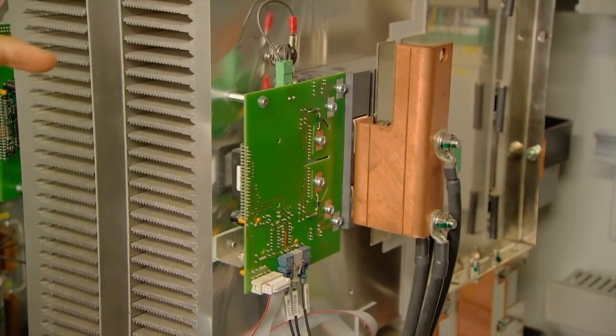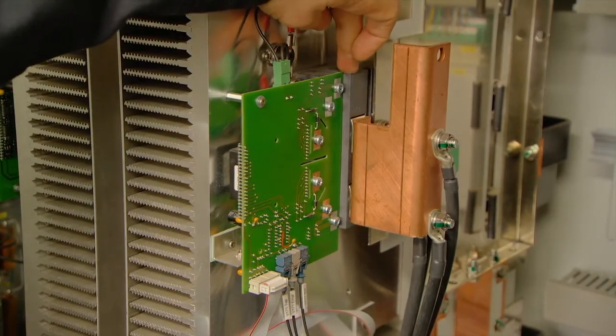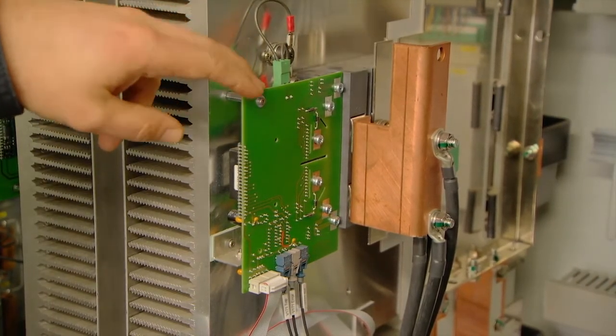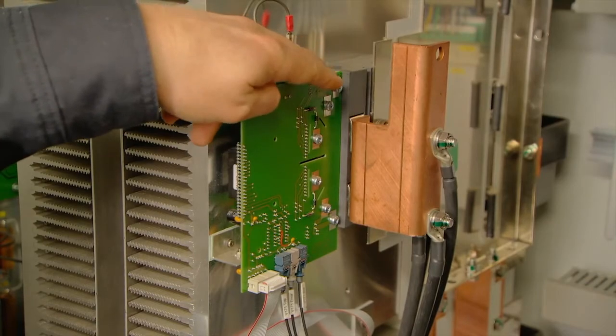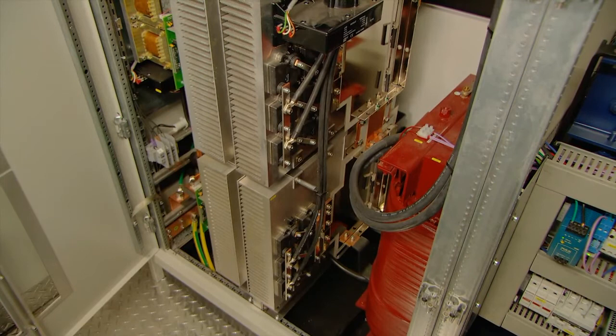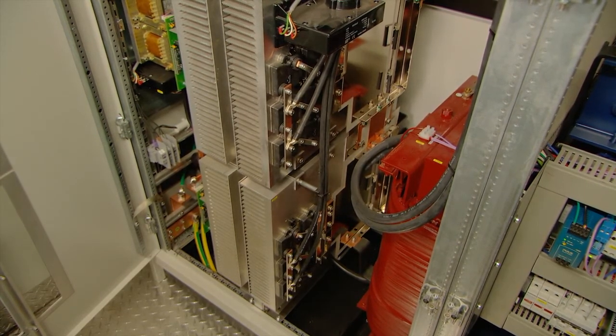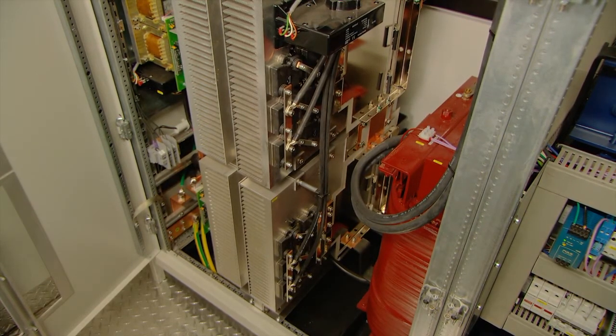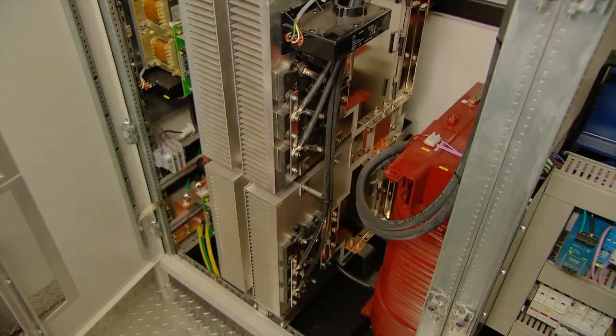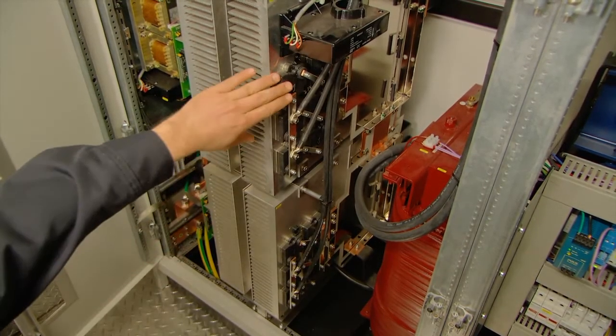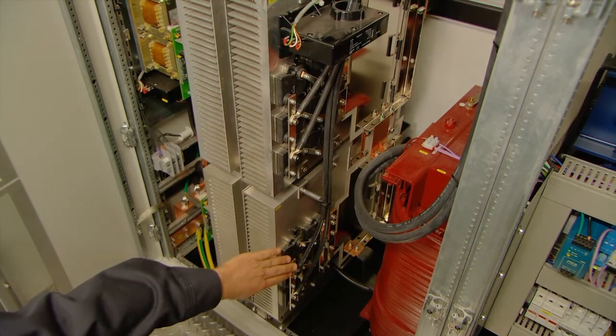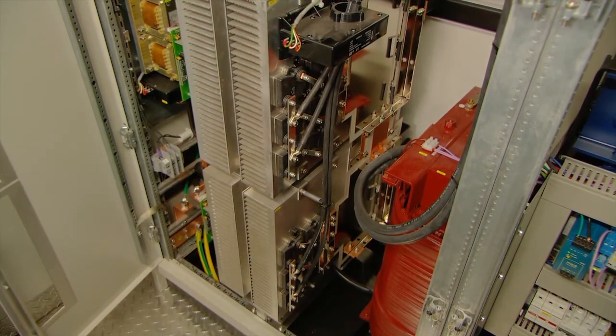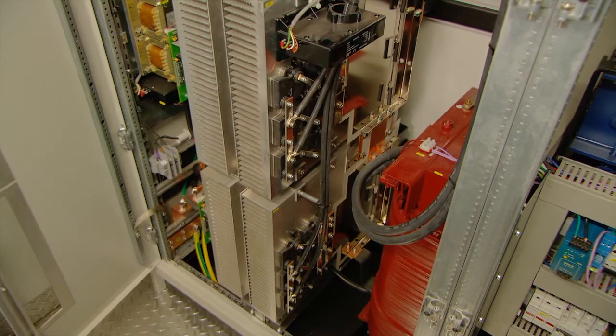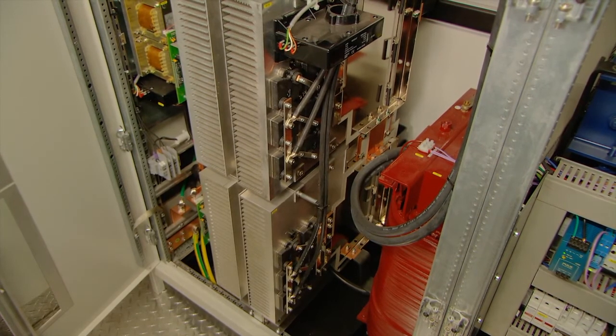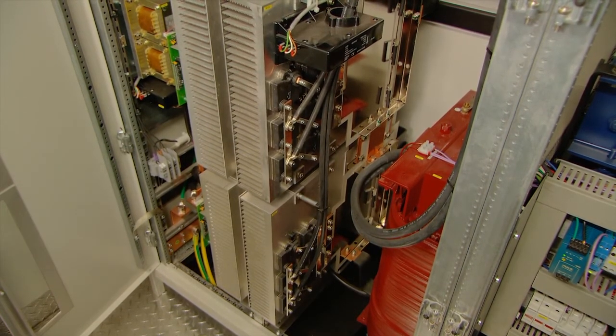On the output DC link there is an IGBT in the black box with its control board. This control board and the IGBT together form a chopper. If the voltage at the output stage is too high, the chopper can burn the excessive energy in the chopper resistors. There are 2 sets of chopper resistors, one at the top and one at the bottom. Each set consists of 6 resistors where the energy is burned. Each resistor takes approximately 100 watt.